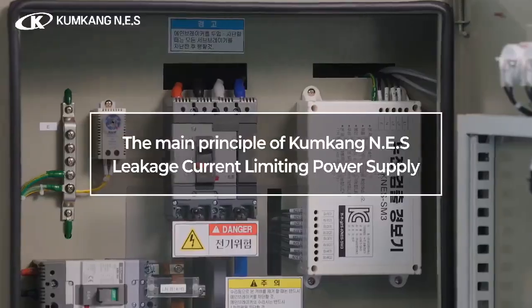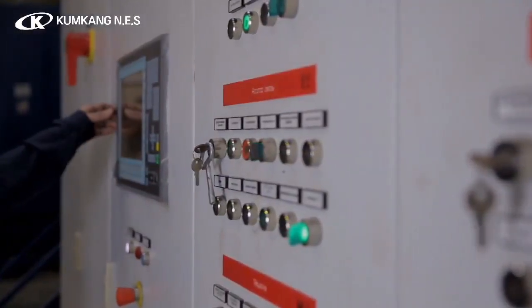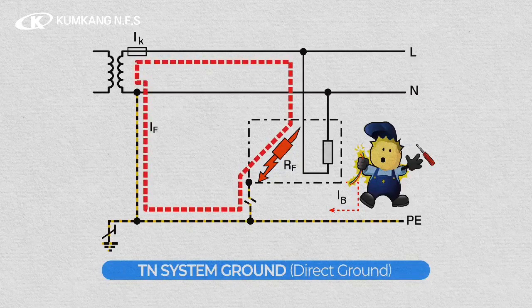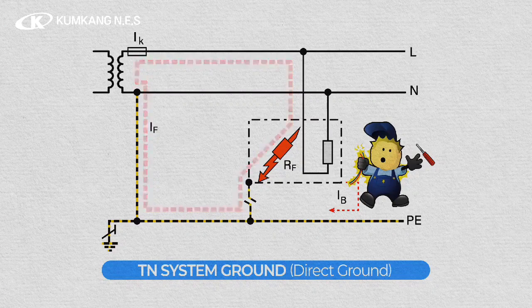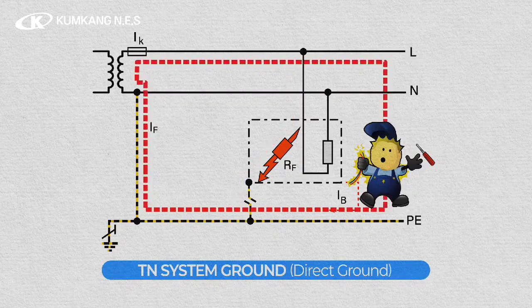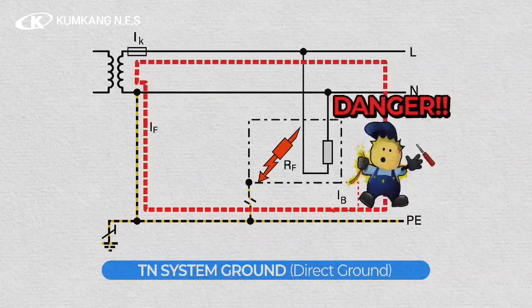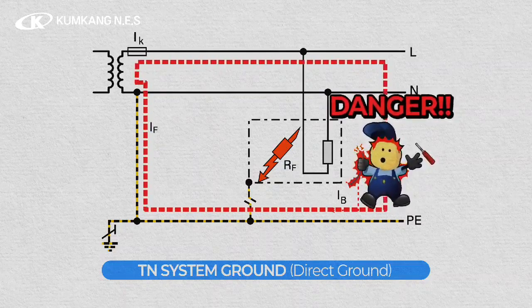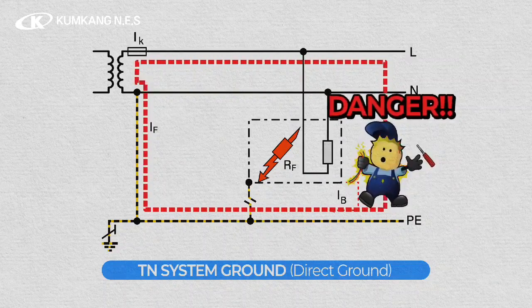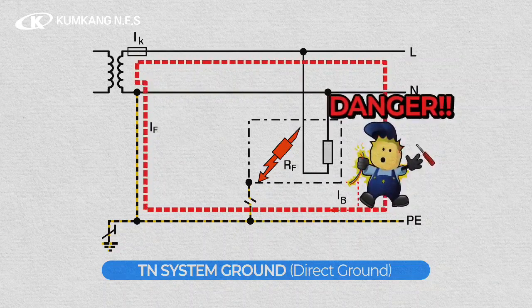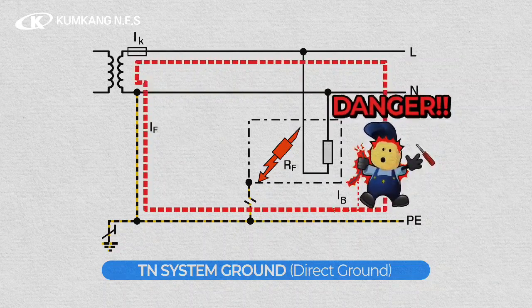The power and current use has a TN or TT type in which the power system is directly grounded. As shown in the diagram, in the situation where a person gets shocked by electricity, the leakage current is only limited by the body's resistance, and high leakage current flows through the ground, posing a risk of electric shock.